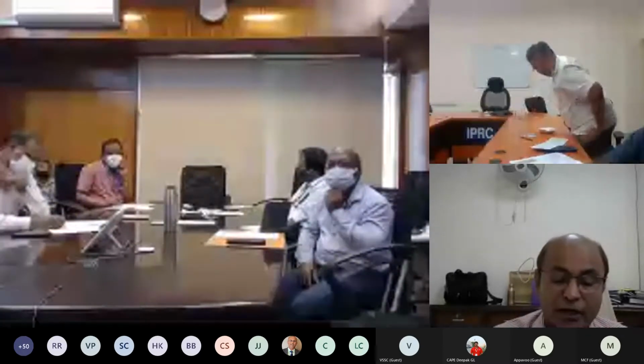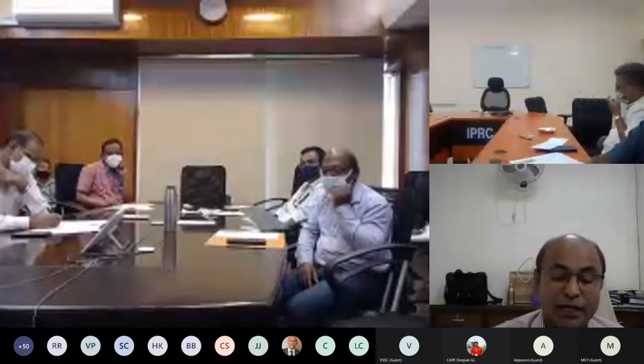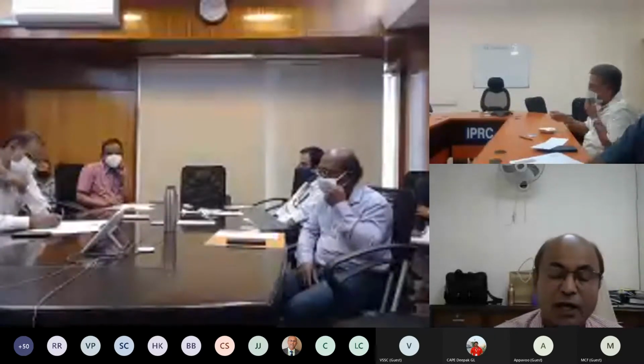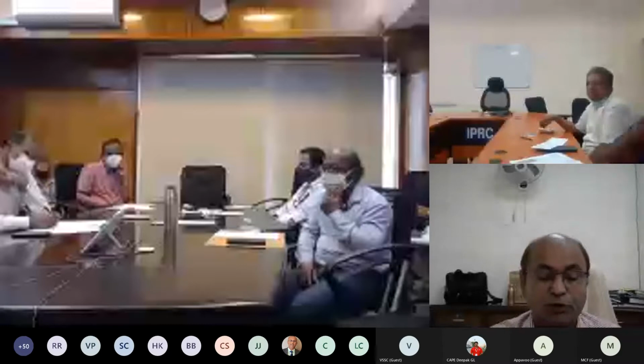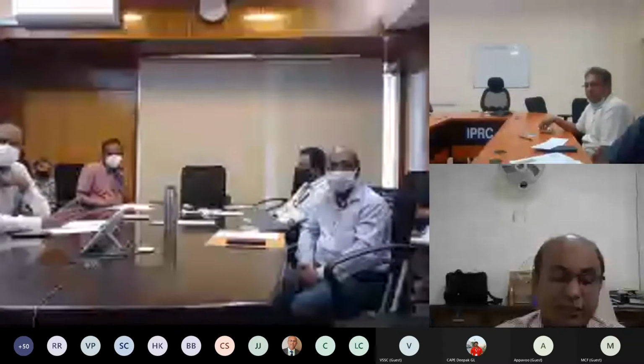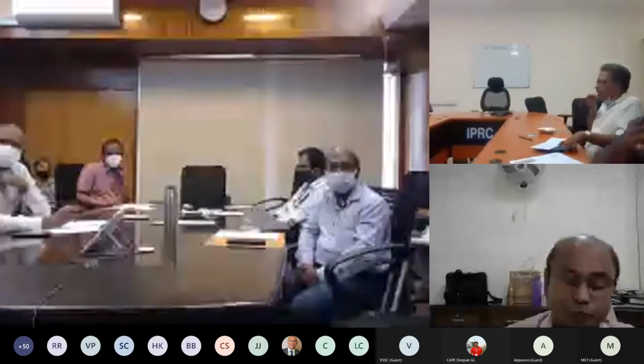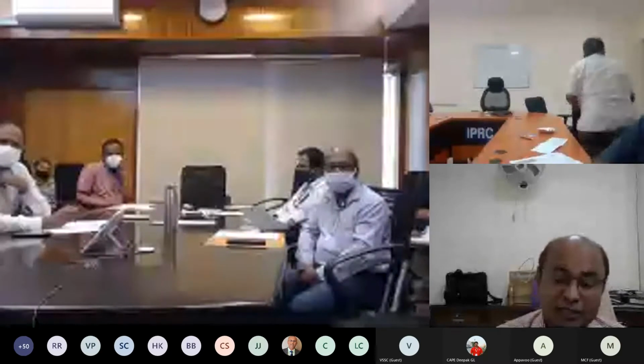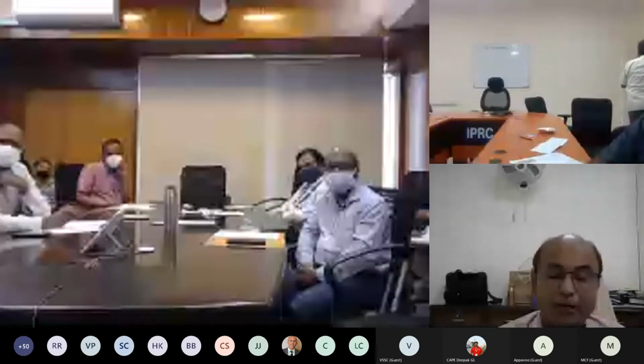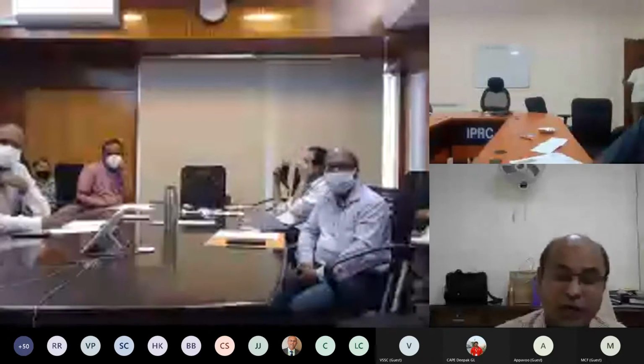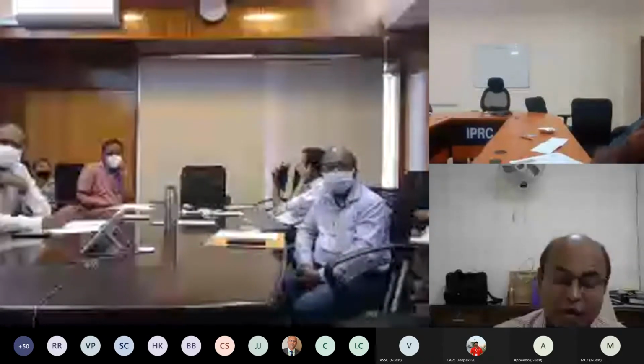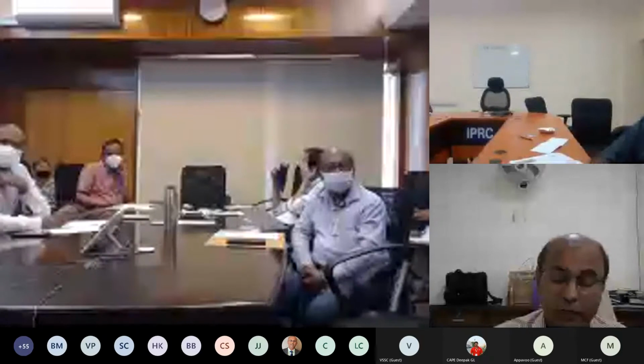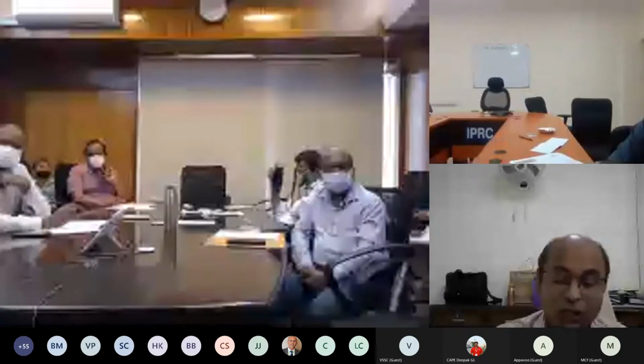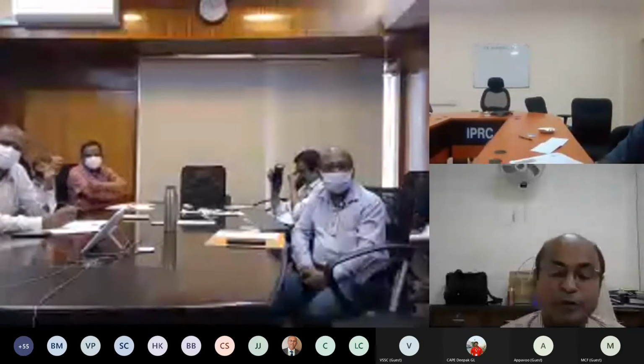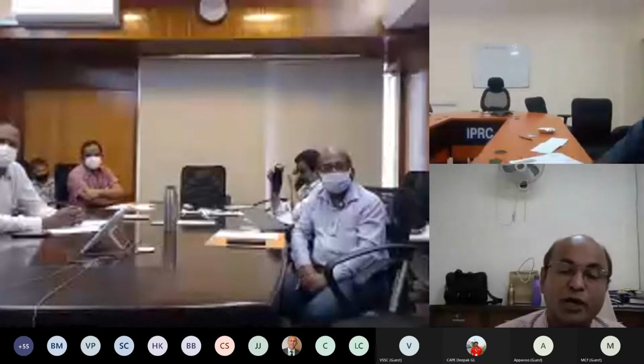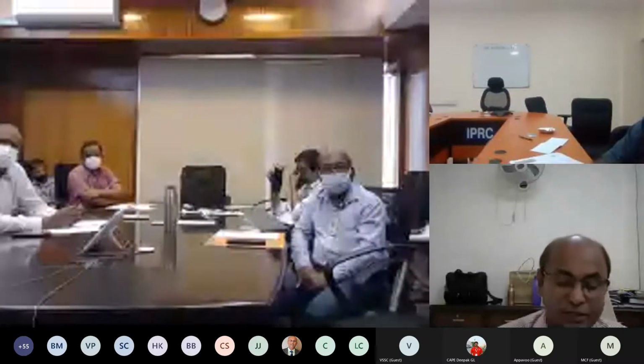In June last year, a fatal accident took place in a housing colony at Ganjam, Odisha, where a helper got electrocuted while replacing an insulator on an 11 kV overhead line supplying power to the housing colony. The line was isolated from one end, but it got back-charged when the DG set supplying power to the colony housing society was on. This accident could have been prevented if the section had been isolated from both ends.